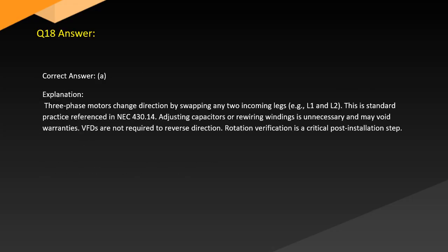Answer. Correct answer: A. Explanation. Three-phase motors change direction by swapping any two incoming legs, L1, L2, L3. This is standard practice referenced in NEC 430.14. Adjusting capacitors or rewiring windings is unnecessary and may void warranties. VFDs are not required to reverse direction. Rotation verification is a critical post-installation step.